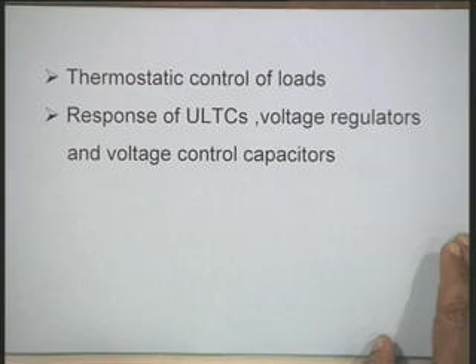Whenever the system voltage dips or becomes low, these ULTCs will try to operate and regulate the voltage. Suppose at a particular time the voltage has dipped. Then the on-load or under-load tap changers will operate to increase the voltage, but the response time is quite high. The voltage is low; after about 1 minute they start operating, and their operation is completed in about 1 or 2 minutes. They are slow devices.